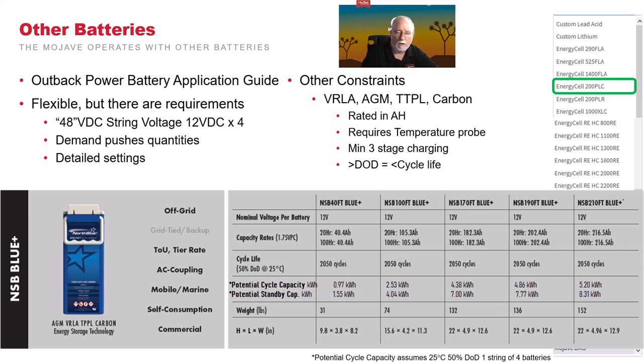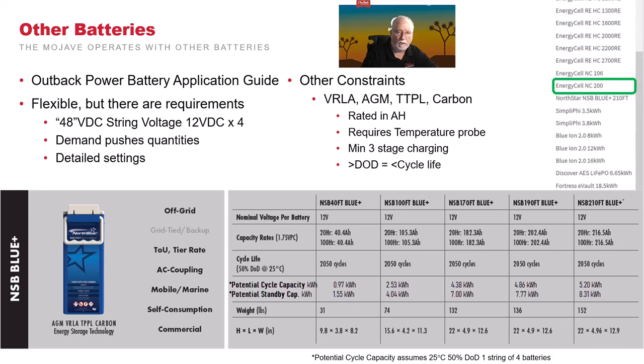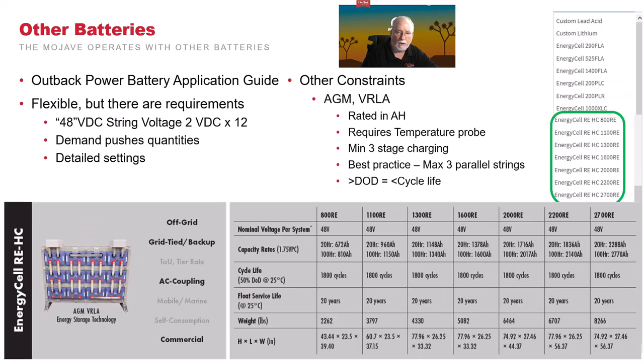They work very well. One thing you'll notice is that I've taken the ampere hour settings and actually converted it to kilowatt hours. These kilowatt hour settings are actually based either on cycle capacity or standby capacity. Cycle capacity, you can see in the notes down in the bottom, is 25 degrees C, 50% depth of discharge. So that's your cycle count for those. Then if you look at the lower setting, the potential capacity is much higher, but that's taking it down to 80% DOD. This is for more of a standby use. So these can be configured in any way, very, very easy to set. All you have to do is go down to the drop down, pick them out, and you're all set.